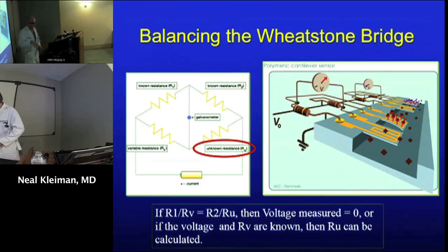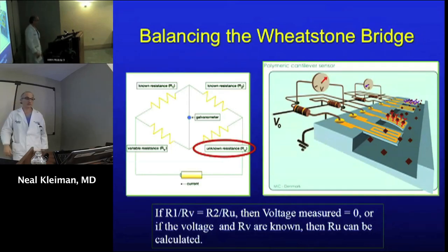Back in the day, the nurse doing the monitoring used to spend a long time balancing the circuits, making sure zero was set properly. That's now simply a push of a button. But back then, the nurse had to adjust a dial, going back and forth, taking a fair amount of time to balance those resistances so you knew the pressure at the low end—called zero—and at the high end, according to the scale. Every time you changed scales, you had to balance it again. These days, this is built into the back of the transducer.